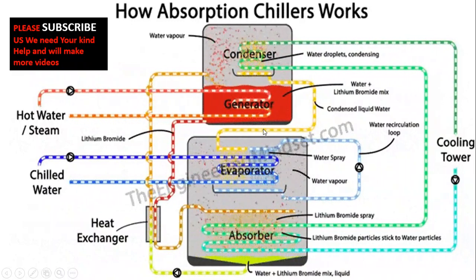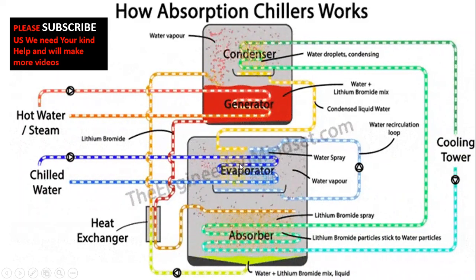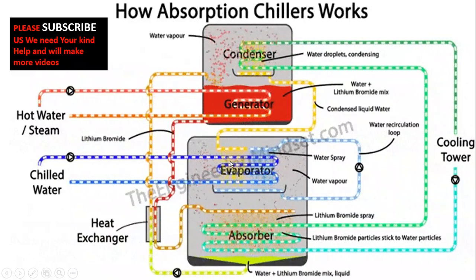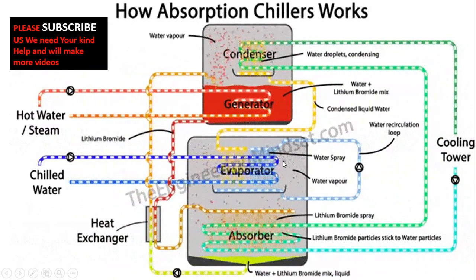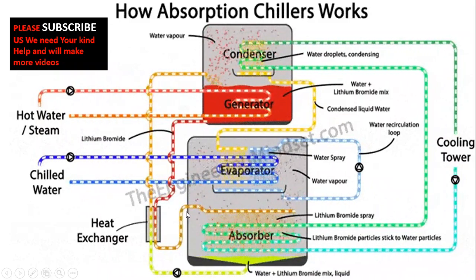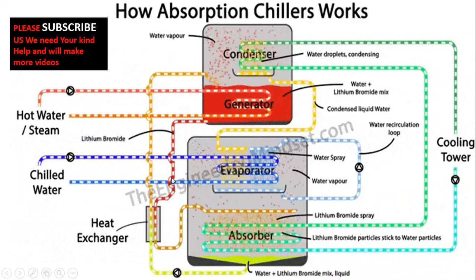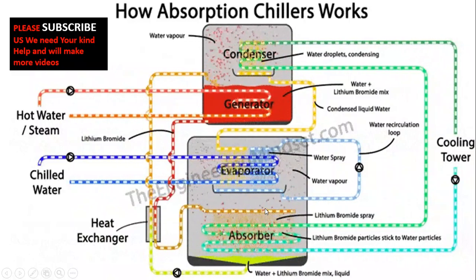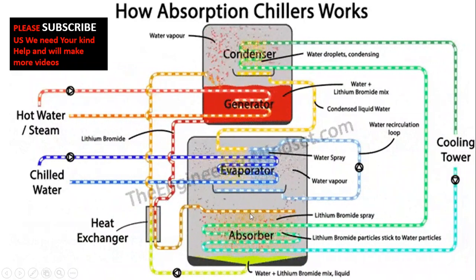This pure water then moves to the lower-pressure chamber. In the evaporator, the water falls onto the evaporator coil carrying fluid from the factory hall, absorbs energy, and becomes gaseous again. The lithium bromide solution passes through a heat exchanger, loses some energy, and is then dropped into the absorber where it mixes with the water vapors already present.